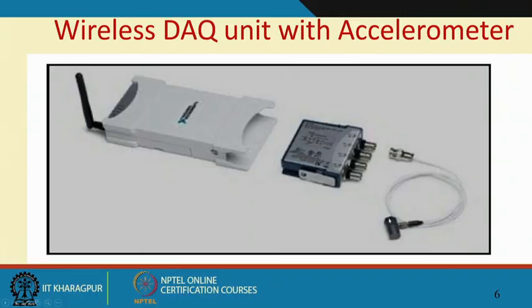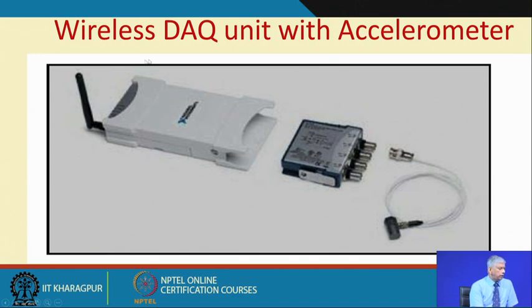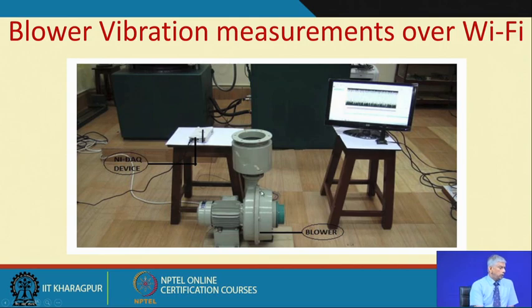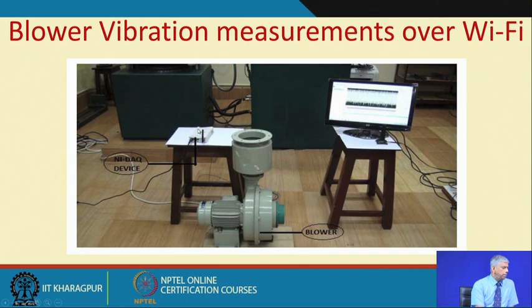We demonstrated this in the laboratory. The data acquisition unit has an accelerometer used to measure vibration — it connects at the machine end through a cable, but the entire unit is kept at the machine and there is a Wi-Fi transmitter which transmits the signal. In the laboratory we have a blower — actually a three-phase motor — with an accelerometer mounted on it and the Wi-Fi device attached. All the cables go in, the blower was run at a certain speed, data was acquired and transmitted. Another laptop with the Wi-Fi receiver received the signal and we can see the time domain signal.